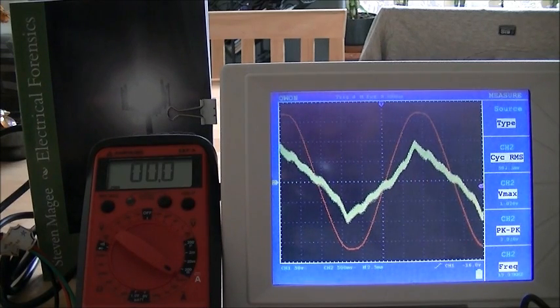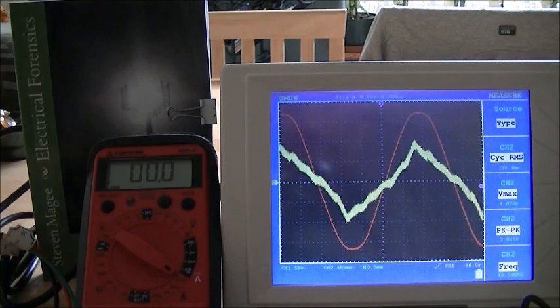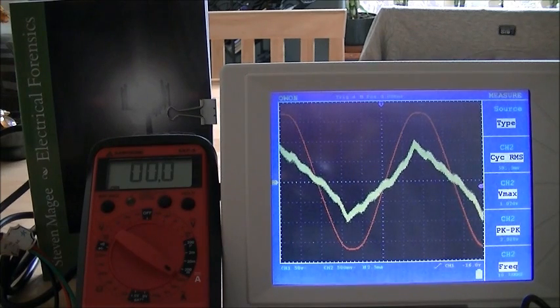We're going to connect it in a minute and we have on the right an oscilloscope. In the red you can see the AC waveform and in the yellow you can see that we have stray voltage on the grounding system.